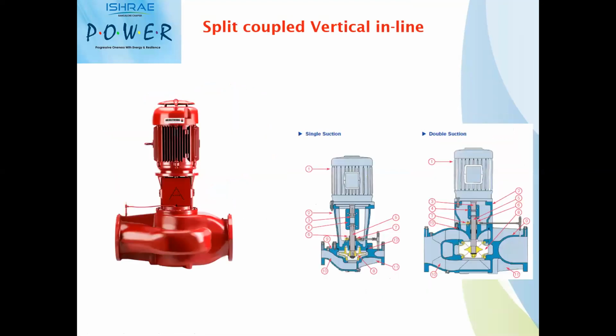Vertical inline design pumps are available in the market where you have suction and discharge on the same side of the same line, where water enters on the suction side and goes out on the discharge side. So here, this is the inlet, this is the outlet, the coupling. It is called a vertical design because the motor is mounted vertically on the pump.